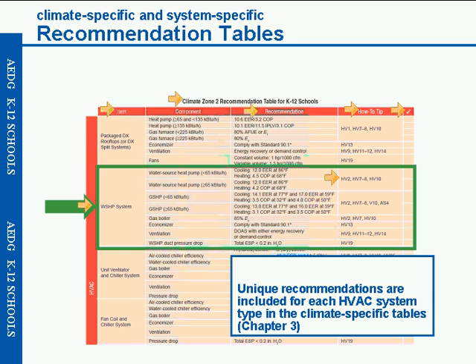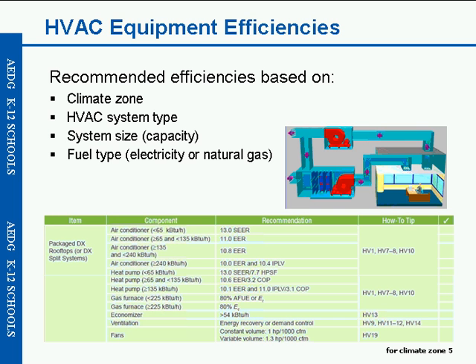As far as the HVAC equipment efficiencies, these recommended efficiencies are based on the climate zone, the HVAC system type, the size of that system, as well as the fuel type. The guides were restricted to either electricity or natural gas as the fuel types that are available. The table at the bottom is for climate zone 5, and it's an example showing package DX rooftops or DX split systems. Again, showing the different sizes in the second column, as well as the recommendation for the SEERs or EERs or COPs, and for furnaces, the annual fuel utilization efficiency.